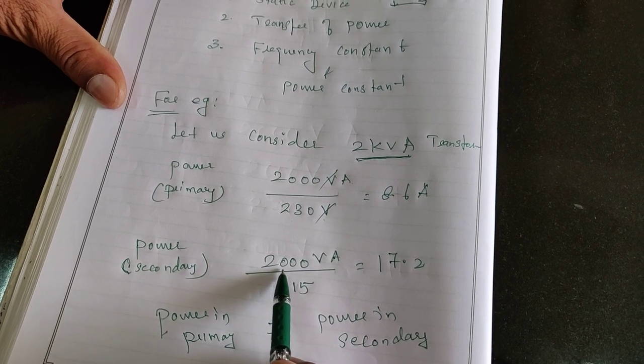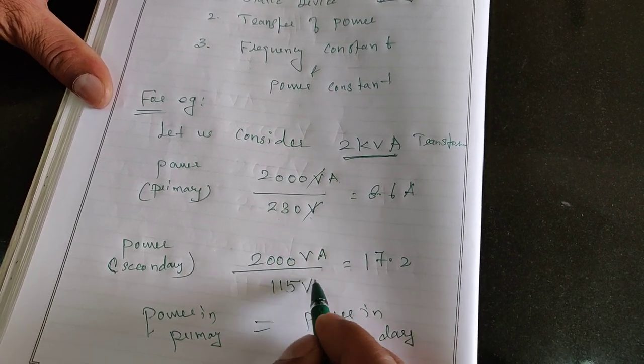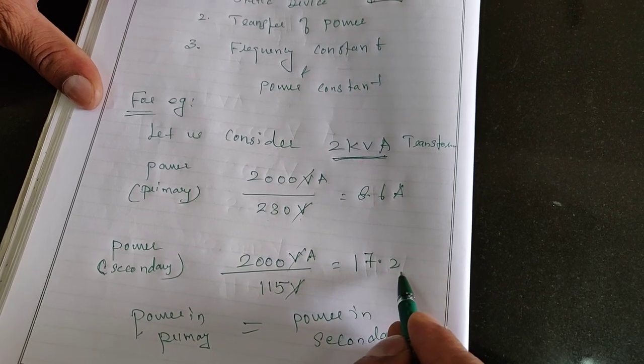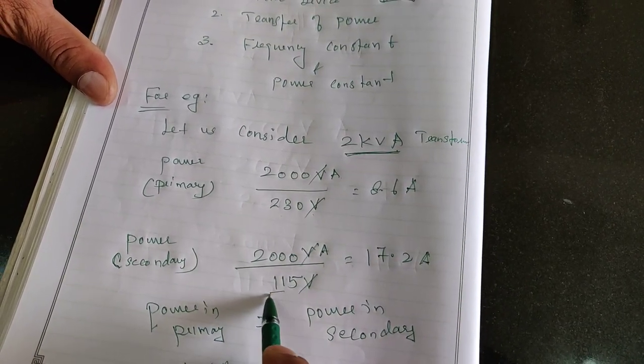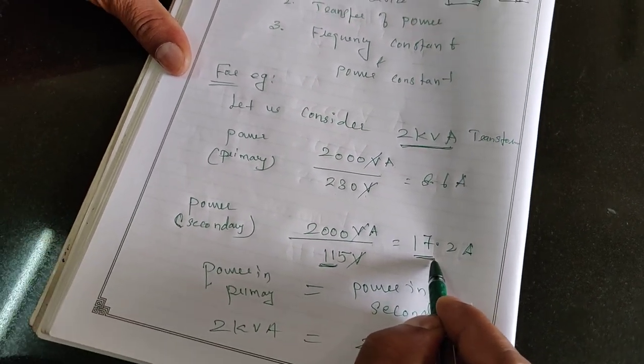Similarly, go to the secondary side. The same 2000 VA divided by 115 volt. Therefore, we will get 17.2 amperes. It means when we have the low voltage, there is the chance for giving more load.